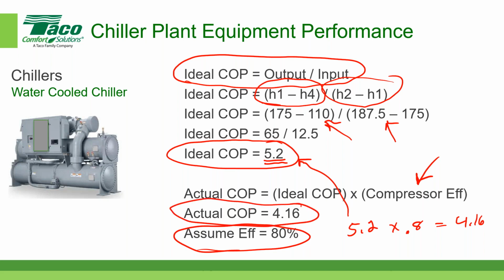So all the numbers that I presented to you right now show you that the best you could possibly do under this scenario of temperatures is 5.2. Then if you add the efficiency in there, and I just arbitrarily made it 80%, if your efficiency was slightly higher than that, then your actual COP would be higher than 4.16. But based on the numbers, you cannot get higher than 5.2 based on the temperatures and the pressures that I had listed in the pressure enthalpy diagram.